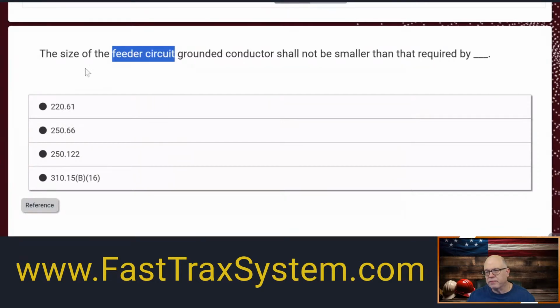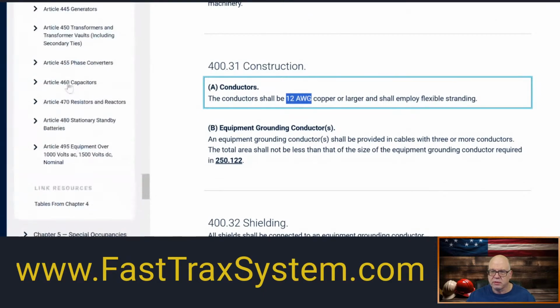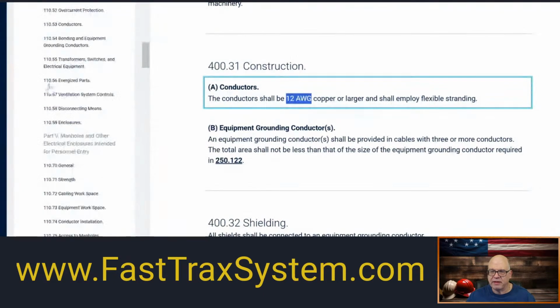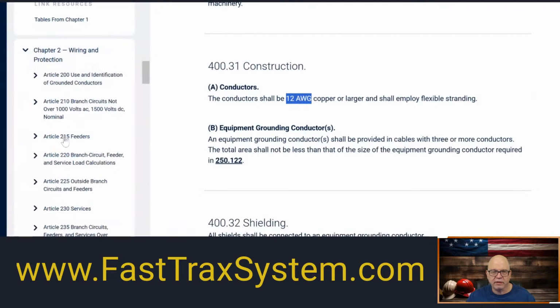Don't we have an article that is dedicated to feeders? Absolutely we do. And a lot of people get confused with that because we have 210 for branch circuits, we have 215 for feeders, and we have 225, which is outdoor branch circuit and feeders, right? And so that's 3 areas that are dealing with different types of circuits, whether it's branch circuit, whether it's a feeder, or whether it is going outside of the building to another building or something like that. So we have 3 different areas, but this is specifically asking about the feeder, okay? So let's go to the NEC and let's go to 215 because that's about feeders. Right here, feeders.